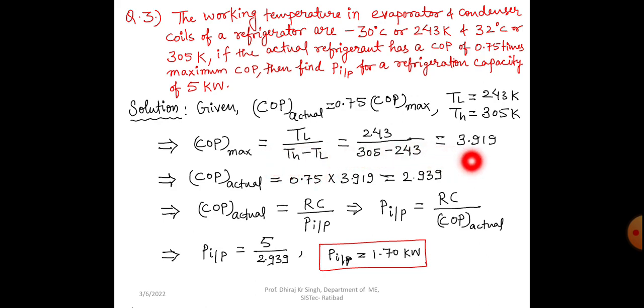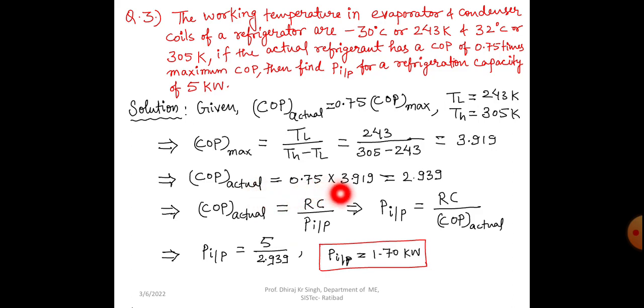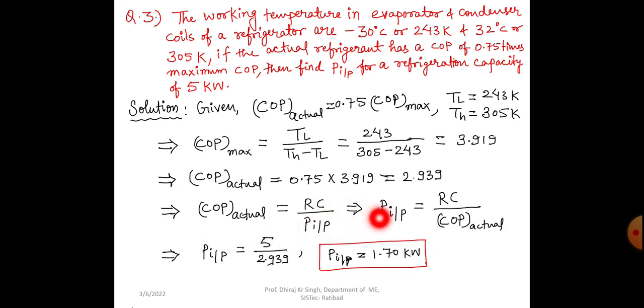Maximum COP is calculated as 3.919. Then COP_actual equals 0.75 multiplied by 3.919, which gives 2.939. Using the formula COP_actual equals refrigeration capacity divided by power input, we can find power input. Finally, the power input is 1.70 kilowatt.